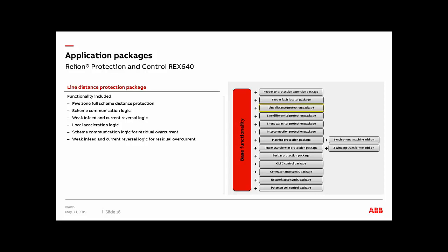Then we have something called local acceleration logic, and it's a complementary function to the distance protection mainly. It is used for those applications where no communications is available, but the user still requires a fast clearance for the faults on the entire feeder. So you can use a local acceleration logic. And then you're going to have, of course, the same schemes, but for residual current, communication schemes, and weak infeed and current reversal as well for residual overcurrent.